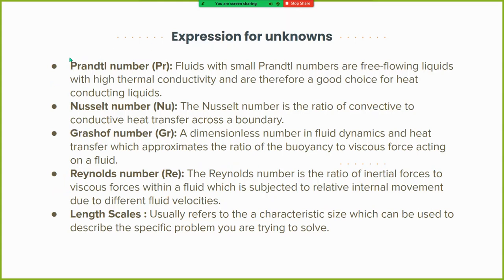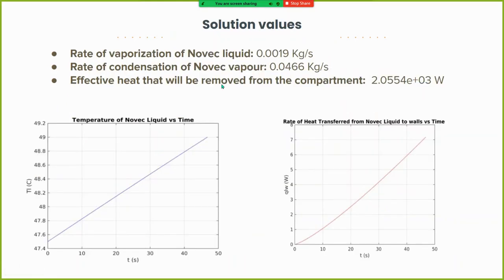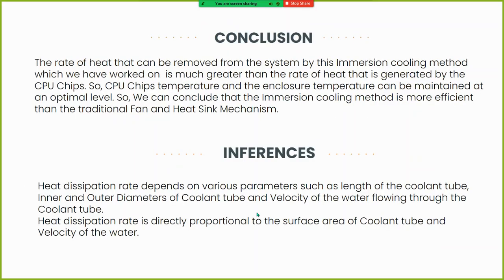The dimensionless numbers used include the Prandtl number, Grashof number, and Nusselt number, used to determine the values of different heat transfer processes, along with the relevant length scales. Moving to the final solution: we found the rate of vaporization of Novec liquid, rate of condensation of Novec vapor, and the effective heat removed from the compartment. The left graph shows Novec liquid temperature versus time, rising from initial temperature to its boiling point. The right graph shows the rate of heat transferred from Novec liquid to the walls versus time — also a roughly linear relationship.